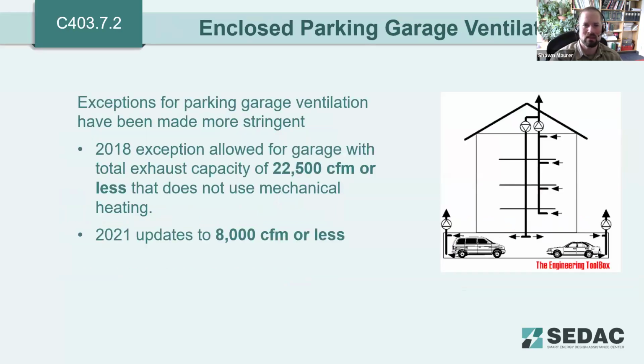For enclosed parking garages, again, some minor updates. 2018 had an exception allowing for a garage with total exhaust capacity of 22,500 CFM or less that did not use mechanical heating to not then have to have ventilation controls for those parking garage spaces. The 2021 updates that CFM limit to 8,000 CFM. So again, making it a little bit more stringent, making this apply to slightly more space types, garage areas.